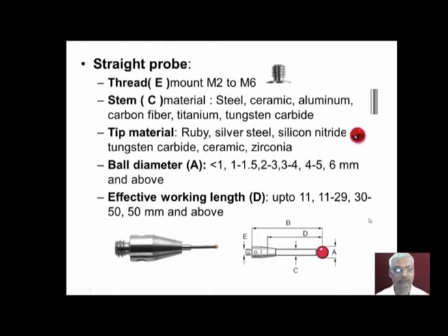Now let us see the details of straight probes. This diagram shows a straight probe stylus. This is the threaded portion which will go into the probe body. Different threads are possible, M2 to M6 threadings are possible, and then this is the stem portion. Stems are available with different materials like steel, ceramic, aluminium, carbon fiber, titanium and tungsten carbide, and they are available with different diameters also. And at the end we have the tip.